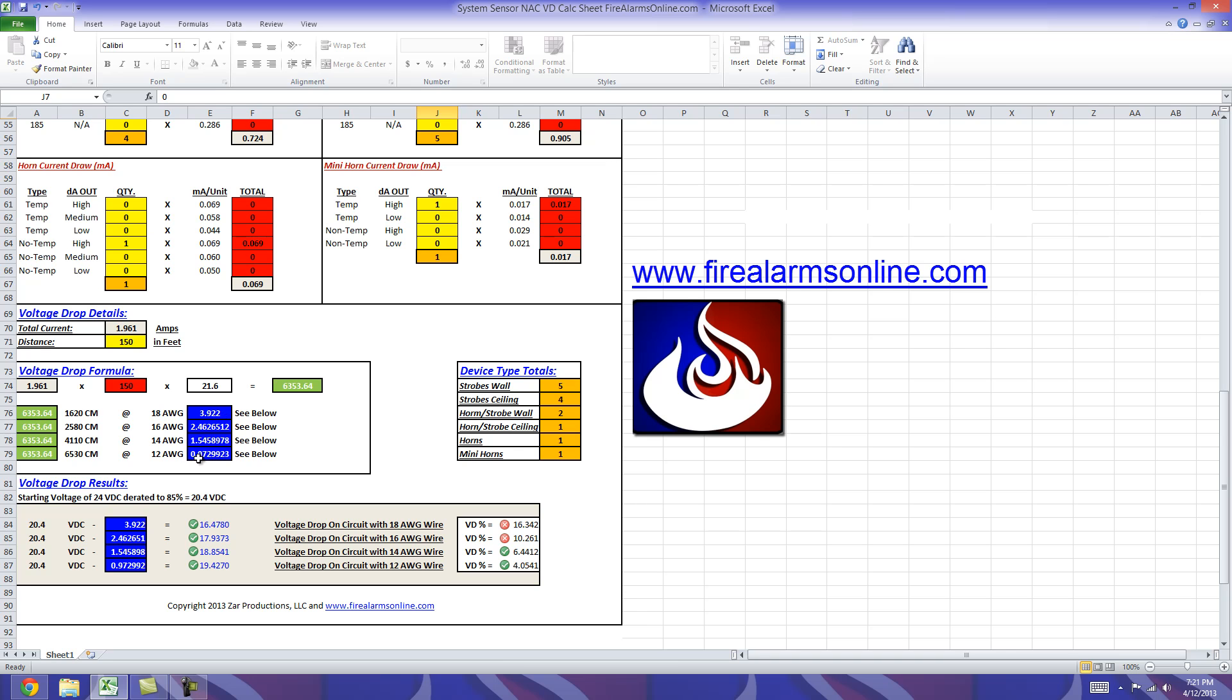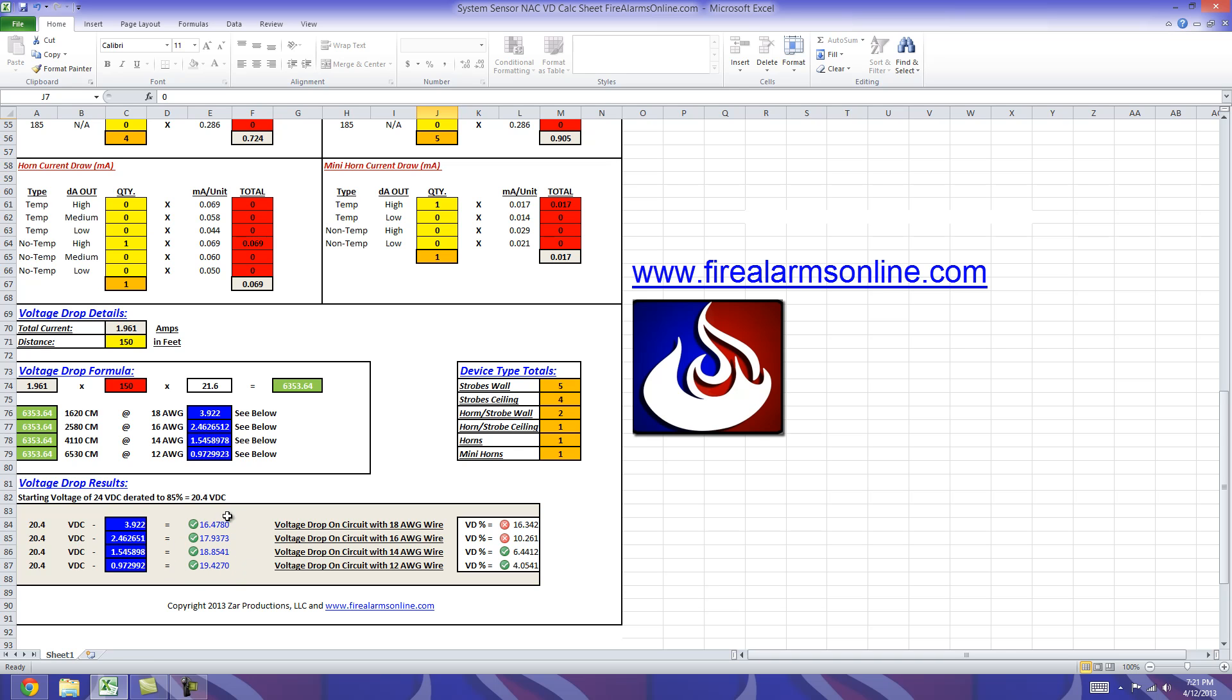So once again sticking with the color theme we move the blue down to here to keep it simple and this is our voltage drop results. Our starting voltage of the circuit is 24 volts DC. We derated that per UL down to 85% which gives us a starting voltage of 20.4 volts. Took that 20.4 volts, stuck it here, and now we're going to subtract our values from our voltage drop formula for each wire gauge type from the 20.4.